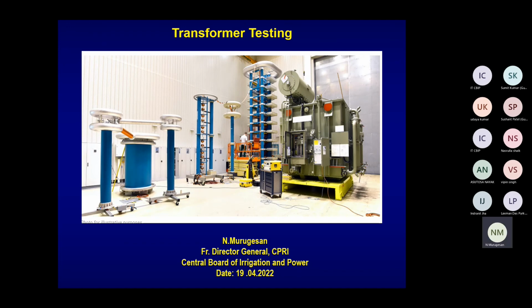So in the normal sense, yes, power transformer because it is not abused like a distribution transformer with overload on all three phases. Because in a substation, you monitor your transformer loading every hour. You monitor it, or automate it such that it gives continuous record of your current and all such things. Now it's automated, so it continuously gives updates on what exactly is going on. So you will never allow it to overload because you are monitoring it.